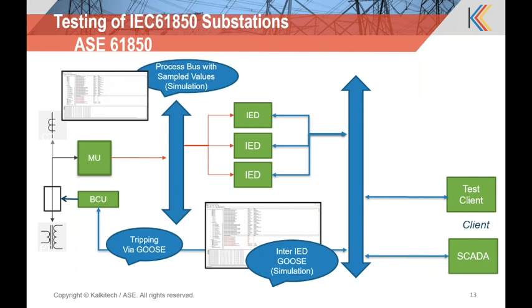So now we will start with the ASE 61850 side of it. So what you see currently is the functionality of a typical 61850 protocol, where you have merging unit functionality on the left-hand side. The merging units will be typically connected to the current transformers and voltage transformers. And further, the data will flow towards the relays, protection relays, and other devices through process bus communication. And further, there will be kind of functionality of protection relays sending data back to the bay controllers to trip the breakers, and the devices will also share the data to HMIs through MMS protocols. So this is the typical architectural diagram of a typical 61850 substation.